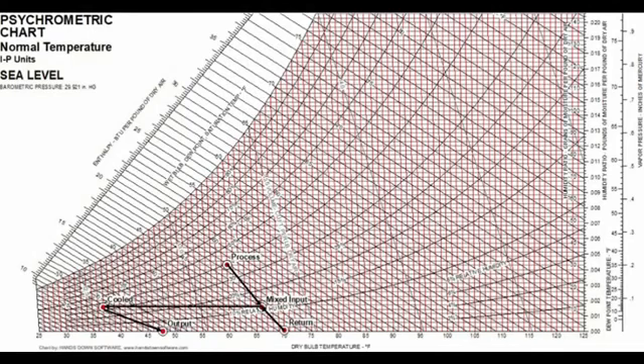This psychrometric chart shows the state of air as it moves through DHU9. The process air is first adiabatically mixed with the dry return air. This mixed air then moves through the cooling coil, which decreases the air temperature but does not decrease the humidity ratio. Then the air moves through the DHU9 desiccant wheel, which lowers the humidity ratio and increases the temperature. In the mixing plenum, the air temperature is then adjusted for human comfort.